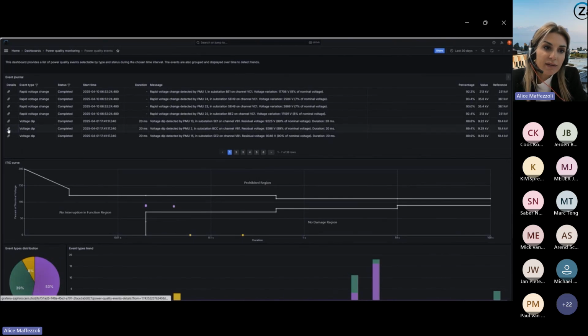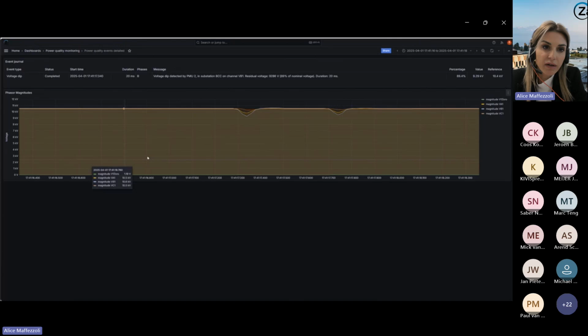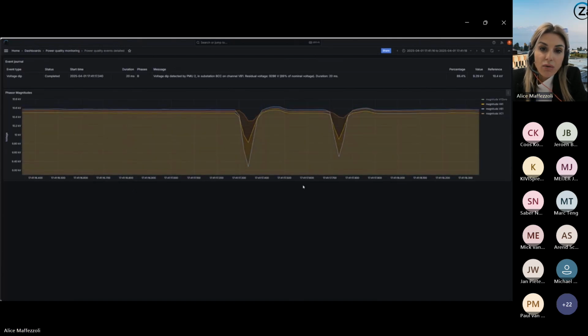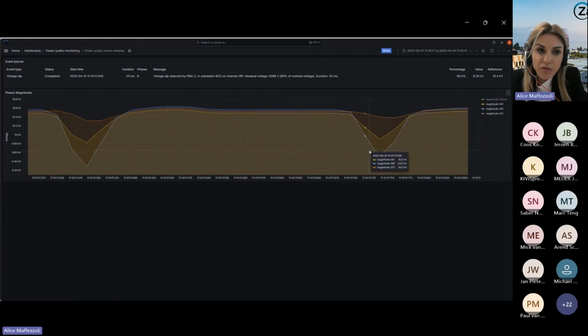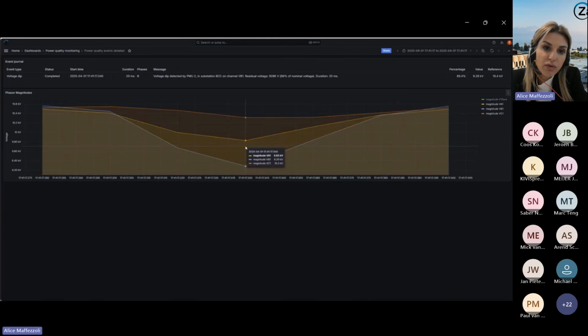For example, we select an event and look at it in particular. We can see what happened in terms of voltage across the whole time frame. We can zoom in and use the pointer to see the magnitude. We also have a message that can be integrated with the SCADA system. In this case, the event was a voltage dip detected by PMU2 in substation BCC on channel VB1, with a residual voltage of 9,286 volts, which is 89% of the nominal voltage, for a duration of 20 milliseconds. So we have a complete set of information on the power quality event.